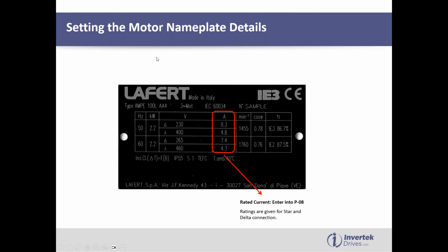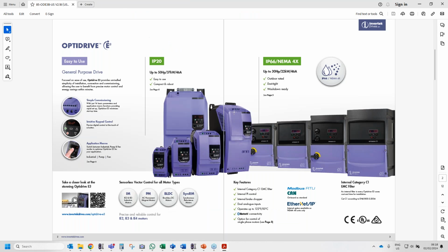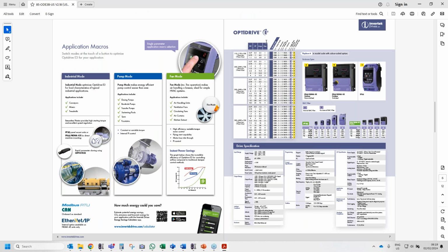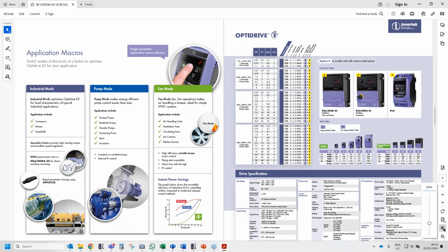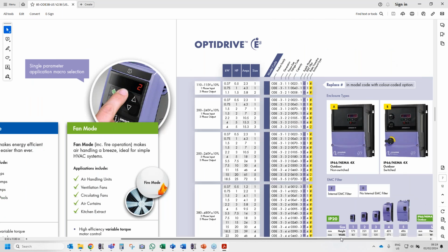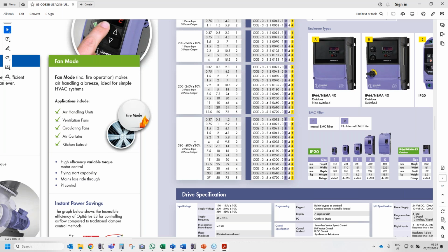I'll just open up the brochure to show you a very simple, quick way of choosing it. Let's do the E3. If you've got a 460 volt system and 4.3 amp, in the product catalog you've got all the features of the drives here, and there's the ratings. I'll zoom in on that. So 460 volt, 4.3 amp. There's the 380 to 480 volt drive. 4.1 amp is too small, so it's going to be a 5.8 amp. It's as simple as that to choose these drives.